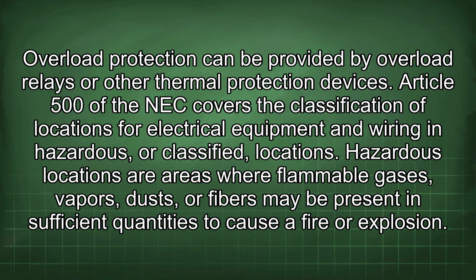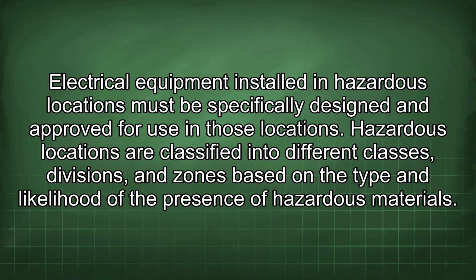Article 500 of the NEC covers the classification of locations for electrical equipment and wiring in hazardous, or classified, locations. Hazardous locations are areas where flammable gases, vapors, dust, or fibers may be present in sufficient quantities to cause a fire or explosion. The electrical equipment installed in hazardous locations must be specifically designed and approved for use in those locations. Hazardous locations are classified into different classes, divisions, and zones based on the type and likelihood of the presence of hazardous materials.